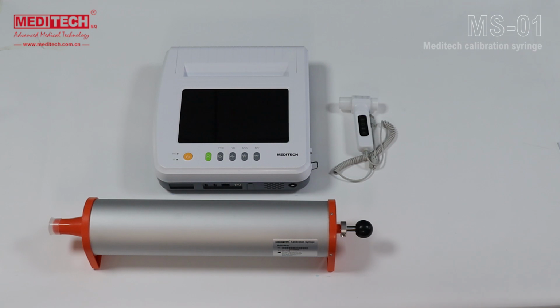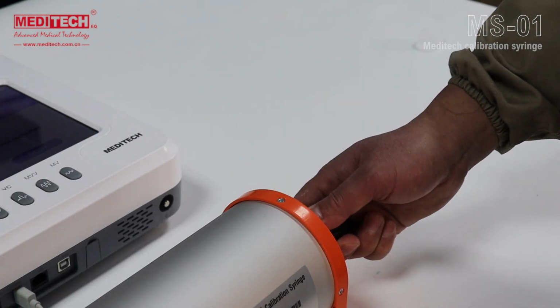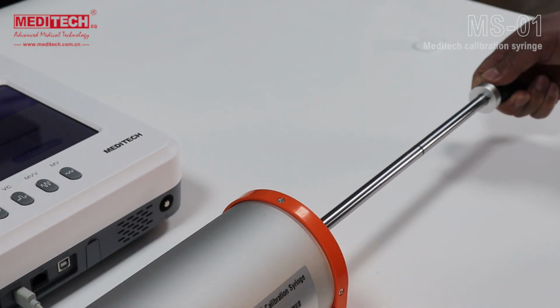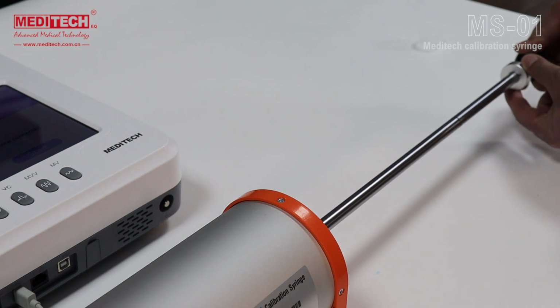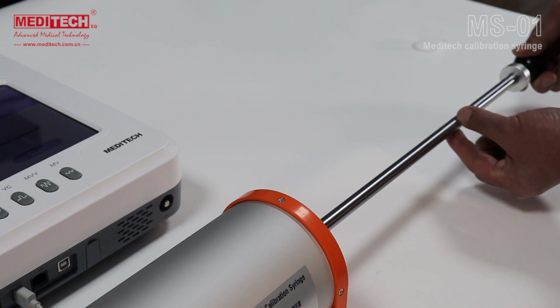The calibration syringe is used for the calibration of pulmonary function tests or spirometry. The maximum calibration capacity of the Meditech calibration syringe MS-01 is 3 liters. It can also be set for a 2-liter calibration test. If you are performing a 3-liter calibration test, this ring must be in this position. If you are carrying out a 2-liter calibration test, you can place this ring in this position.